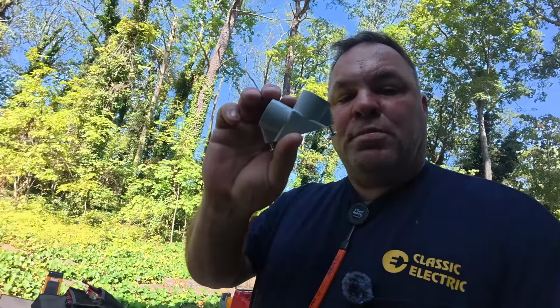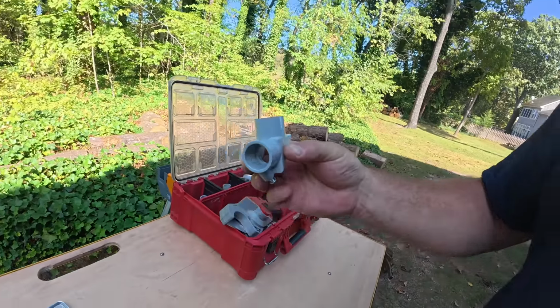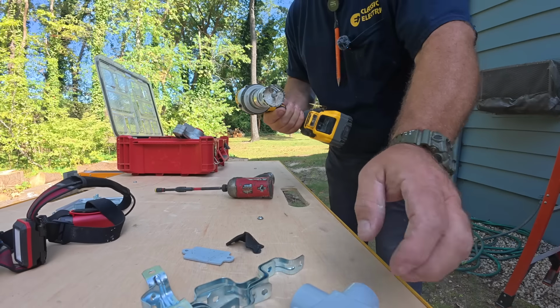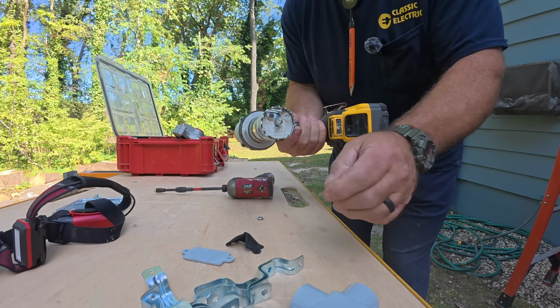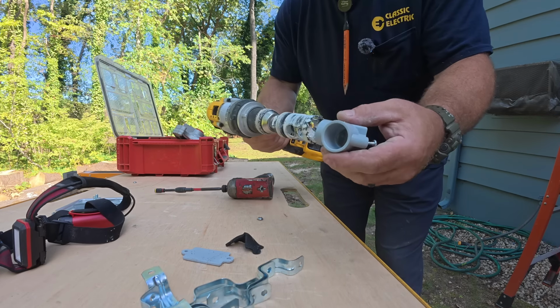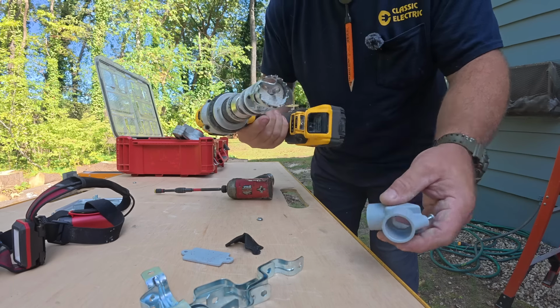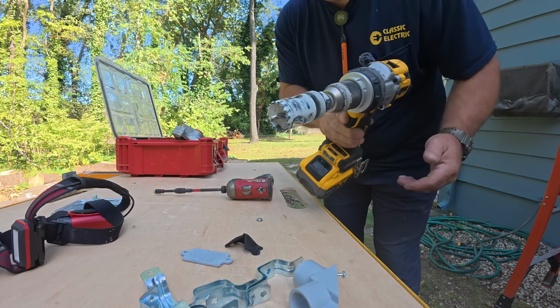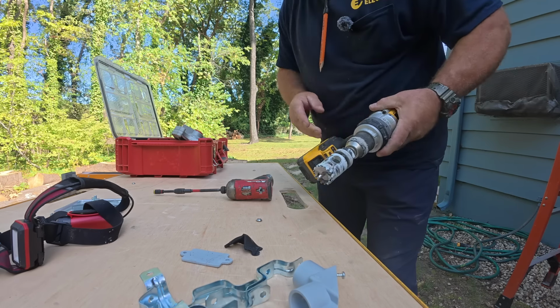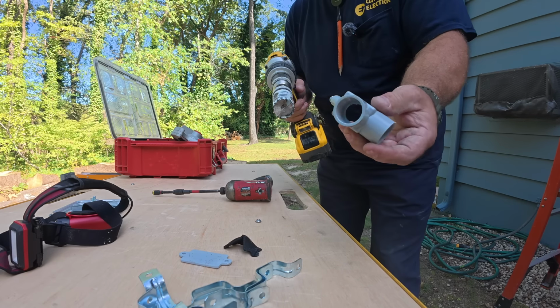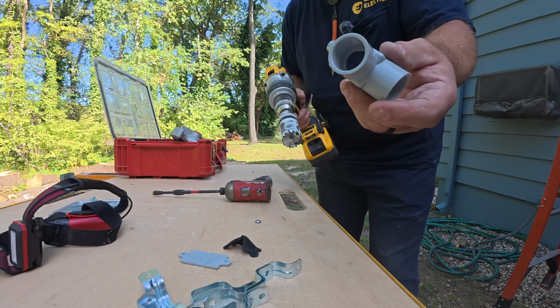I'm going to use this little corner bracket right here to go in the wall, and then we'll stub out inside the basement with some flex, and then we'll transition from the rigid PVC to the flex and go into the panel that way. When at all possible, I like to use a hole saw just large enough to make around this 3/4 inch fitting. I keep this in my 3/4 inch PVC box, and it goes real nice when I want to insert this in the wall. Put a little duct seal and some caulk around that, make that air watertight, and we'll be good to go.